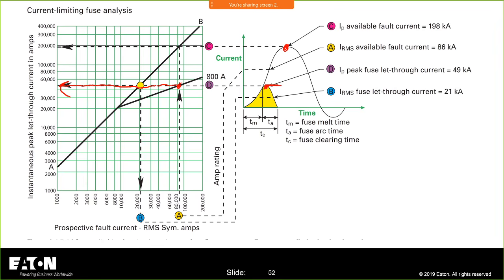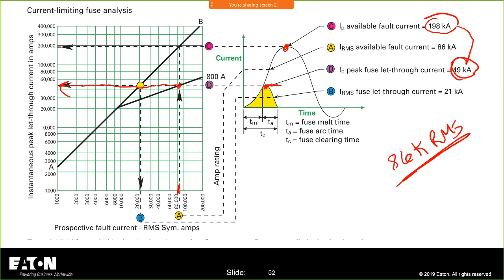So I know for a fault current of 86,000 RMS, so it's 86K RMS, for that fault current value, which is right in here, if I don't have a fuse involved, my peak is 198,000 amps. If I have my current limiting fuse in the picture, my peak current is now 49,000 amps. So I took 198,000 amps and I reduced it down to 49,000. And you know what that does? That reduces the magnetic forces in the system. Reducing the peak reduces the magnetic forces in my power distribution system.